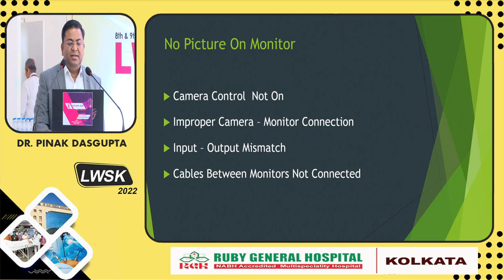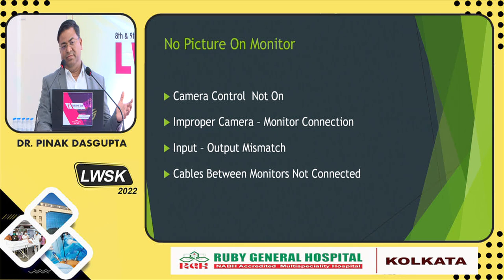Similarly, problems may come in the camera system. One has to check whether the camera is plugged properly inside the camera processing unit, and whether any cable is faulty which connects the vision out to the vision in on the monitor. If there is a break in the cable, that can also cause a problem.